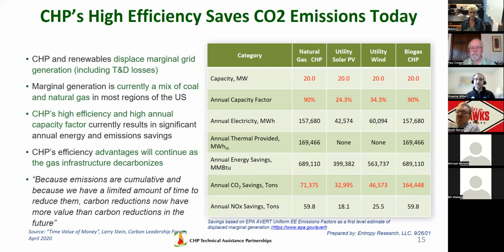However, when you compare similarly sized installations, you also need to compare an annual capacity factor. Capacity factor is essentially a percentage that the unit can operate as a percentage of its maximum output. So if your maximum output is, in this case, 20 megawatts, an annual capacity factor that's fairly standard, if not conservative, for combined heat and power would be 90%. That is, throughout the entire year, combined heat and power is putting out 90% of that 20 megawatts because it runs on natural gas, and unlike solar and wind, natural gas is not interrupted by seasonality.